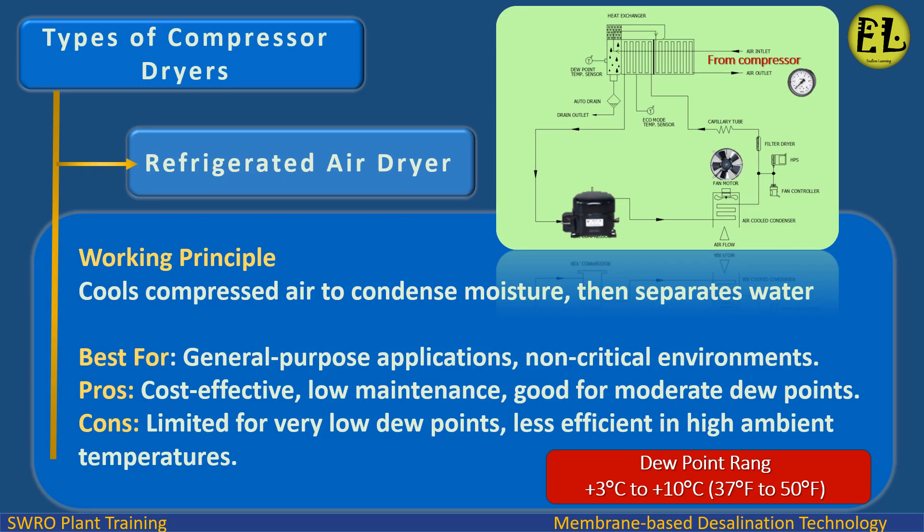Refrigerated air dryer. Working principle: cools compressed air to condense moisture, then separates water. Best for general purpose applications and non-critical environments. Pros: cost effective, low maintenance, good for moderate dew points. Cons: limited for very low dew points, less efficient in high ambient temperatures. Dew point range: 3°C to 10°C (37°F to 50°F).